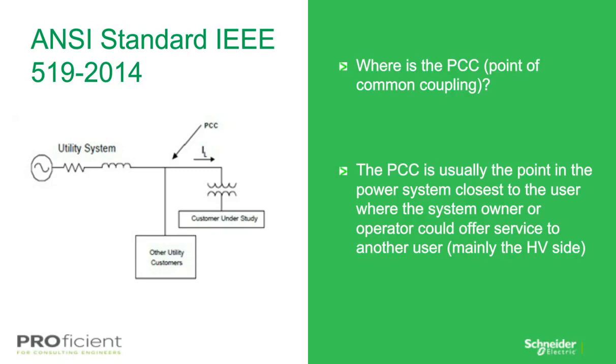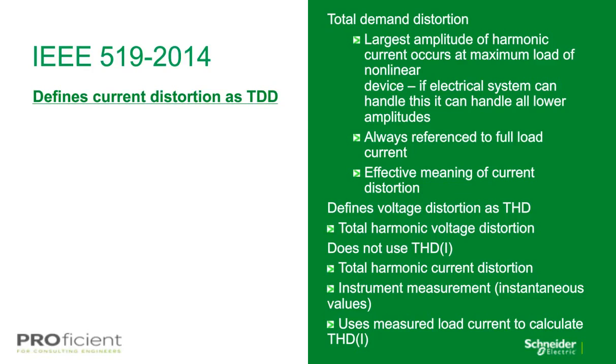So moving on and defining the TDD, also known as total demand distortion, which is the harmonic current distortion level at maximum or demand load for the facility. The THD, the total harmonic distortion, is a term used for voltage distortion measurements. And by definition of IEEE 519-2014, they state the ratio of the root mean square of the harmonic content, considering harmonic components up to the 50th harmonic order, and specifically excluding interharmonics, expressed as a percent of maximum demand current. Harmonic components of order greater than 50 may be included when necessary.